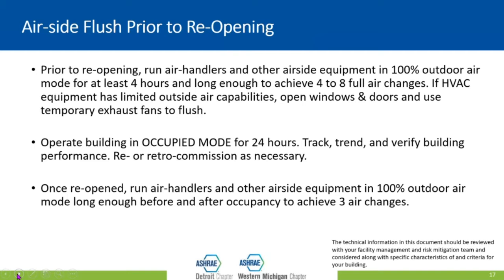After that, you want to operate 24 hours, and you want to monitor and trend all the building performance metrics. Is it able to maintain set point for airflow? Is everything working like it's supposed to? Does anything need to be adjusted or repaired or replaced? You want to be able to answer these questions.